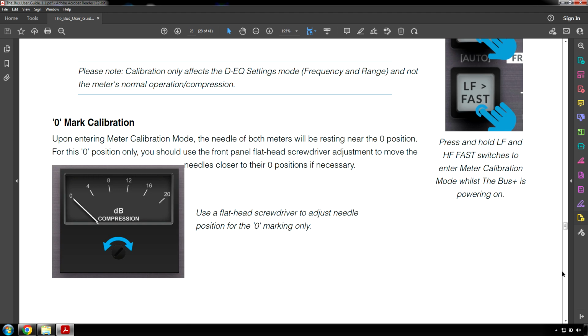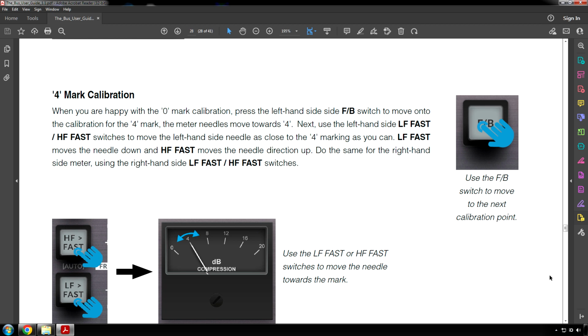0 mark calibration. Upon entering meter calibration mode, the needle of both meters will be resting near the 0 position. For this 0 position only, you should use the front panel flathead screwdriver adjustment to move the needles closer to their 0 positions if necessary. 4 mark calibration. When you are happy with the 0 mark calibration, press the left-hand side FB switch to move on to the calibration for the 4 mark.